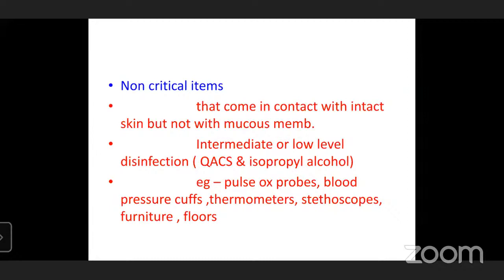For example, items like pulse ox probes and blood pressure cuffs can be cleaned even with an alcohol-based disinfectant. Alcohol-based disinfectant is very fast-acting—it acts immediately after you wipe the surface, but the action doesn't last long, probably just 2 or 3 minutes. You don't get extended disinfectant action on the surface with alcohol, so you use it for non-critical items that don't touch mucous membranes or abraded, damaged skin.